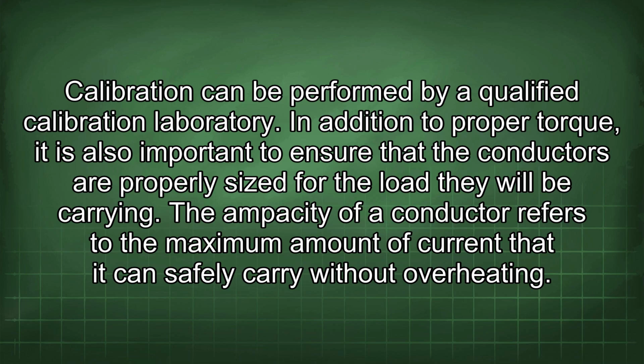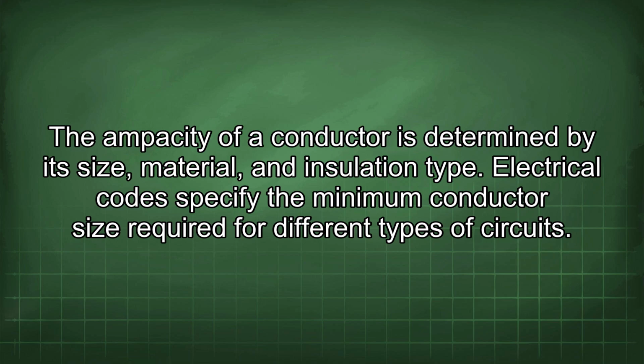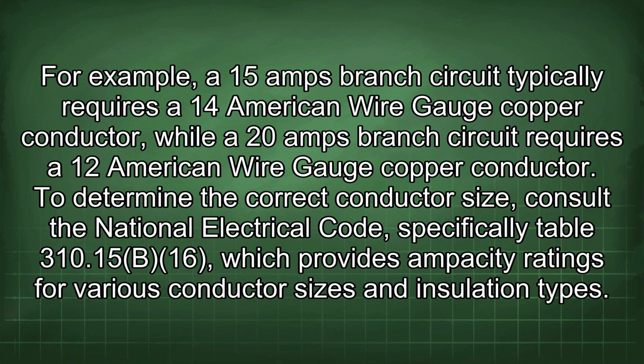In addition to proper torque, it is also important to ensure that the conductors are properly sized for the load they will be carrying. The ampacity of a conductor refers to the maximum amount of current that it can safely carry without overheating. The ampacity of a conductor is determined by its size, material, and insulation type. Electrical codes specify the minimum conductor size required for different types of circuits. For example, a 15 amp branch circuit typically requires a 14 American wire gauge copper conductor, while a 20 amp branch circuit requires a 12 American wire gauge copper conductor.